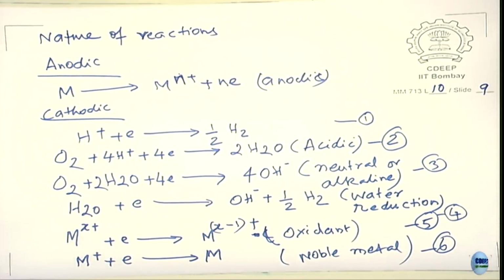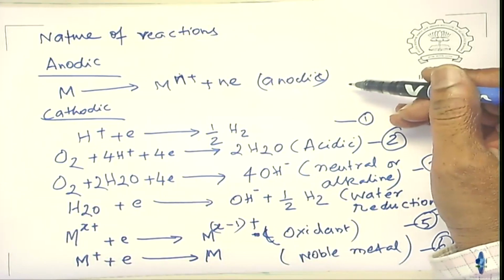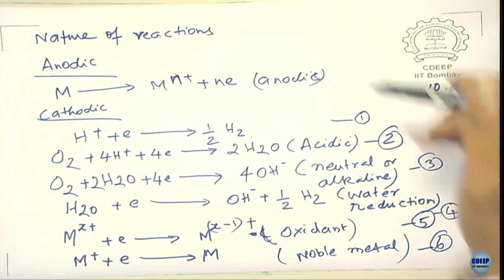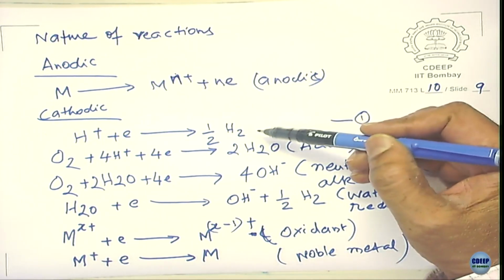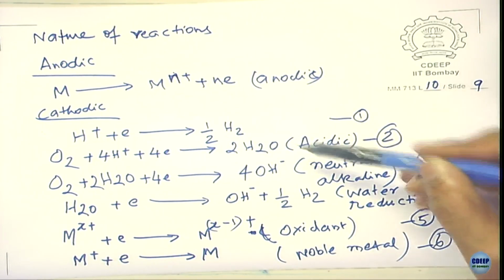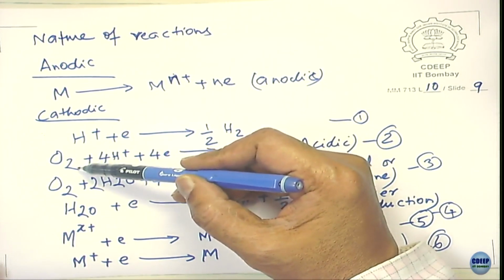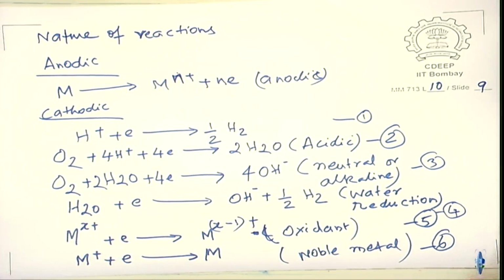So, this is your notes. Right? Tell me, how is it possible that the boiler can be made resistant to corrosion? Yeah, good. So, you know what the cathodic reactions are, you know what the anodic reactions are. You cannot do much about the anodic reaction, maybe you can do a bit, we will come back to this later. First look at the cathodic reactions here. First of all, you get rid of oxygen, you said deaeration. Why? Because oxygen is one thing which is causing problems. So the first thing they do is deaeration.